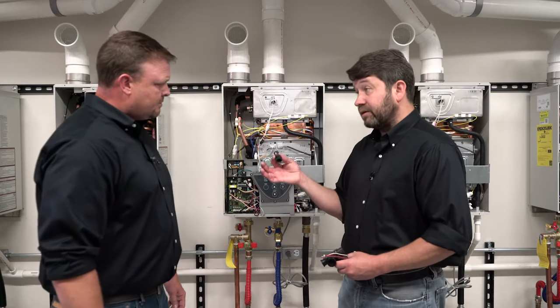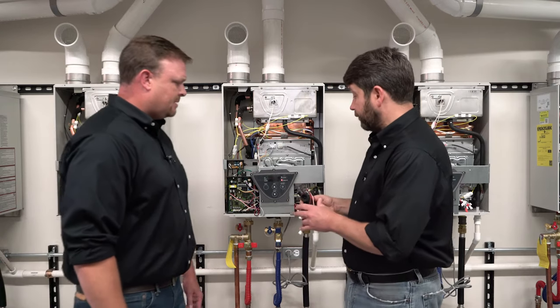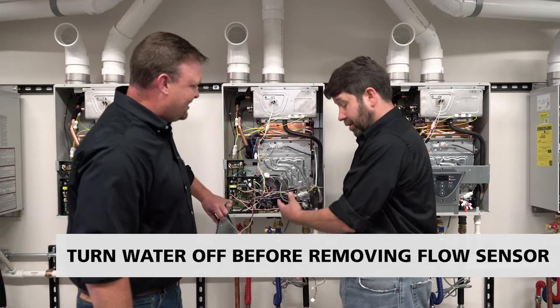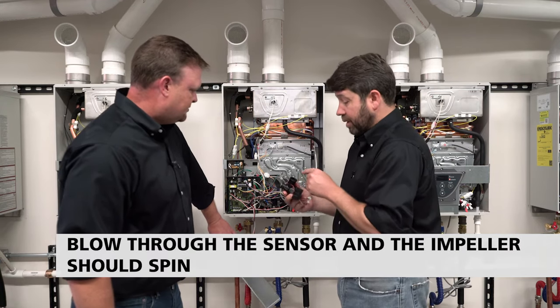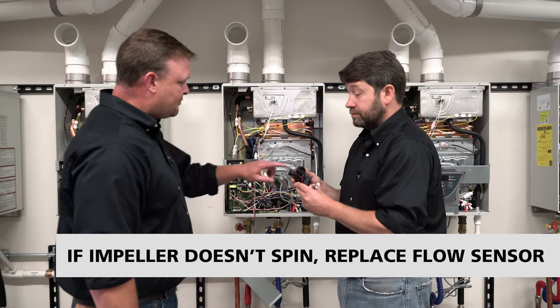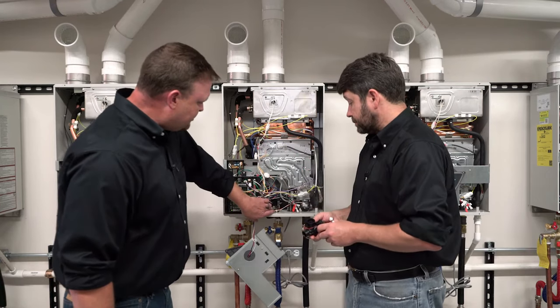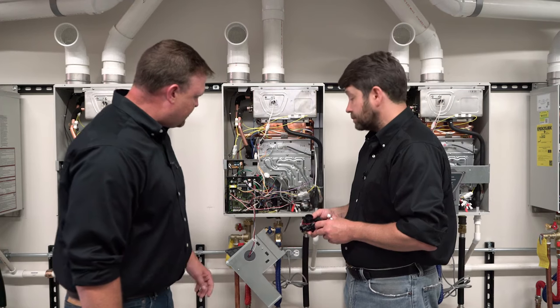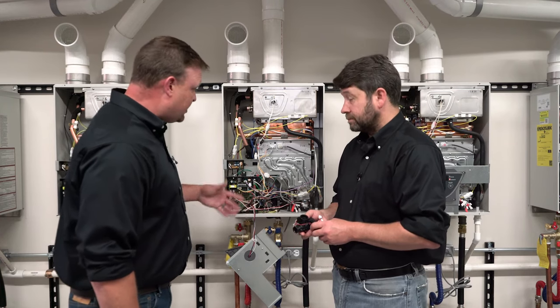Once the filter is cleaned and reinstalled, if we're still getting flow through the heater but it's still not coming on, then we're looking at the flow sensor itself. This is the flow sensor, and two clamps hold it in place. Make sure the water is off before removing the clamps to avoid water damage. This is a pretty easy thing to check — we're just going to blow through it and we should be able to see the impeller spin. If we can't blow through it or the impeller doesn't spin, we need to replace it. We remove the bottom clamp and the side clamp, then just lift it up and over — it comes out pretty quickly.